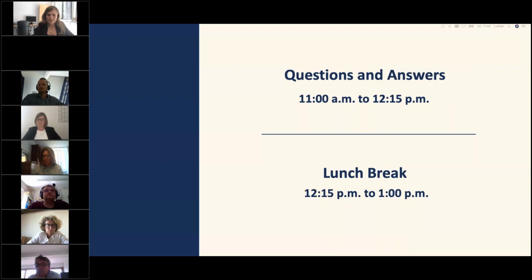I think it would be essential, in case you plan to implement a significant change, that you first get in contact with your notified body and inform them of the planned change, so that there is no wrong work or too much work done within the manufacturer, and also to get the approval that you can potentially implement the change. Because sometimes the notified body would disagree, depending on the purpose and depending on the risk. Thank you for adding this. Thank you.